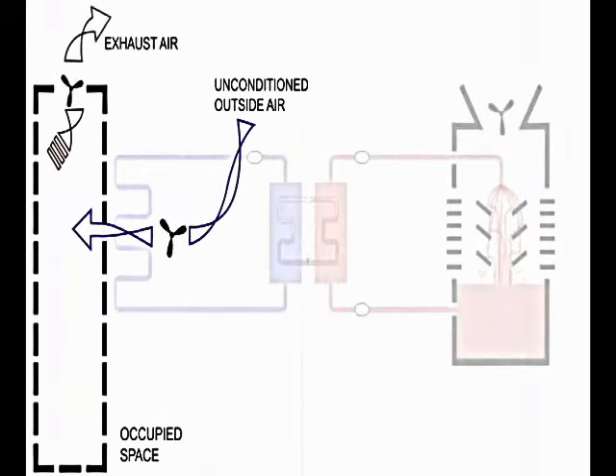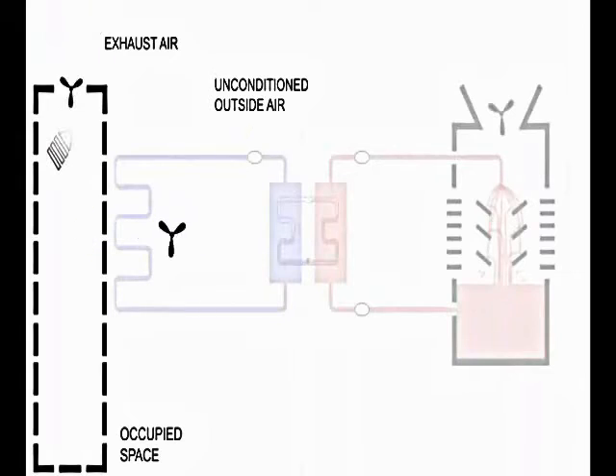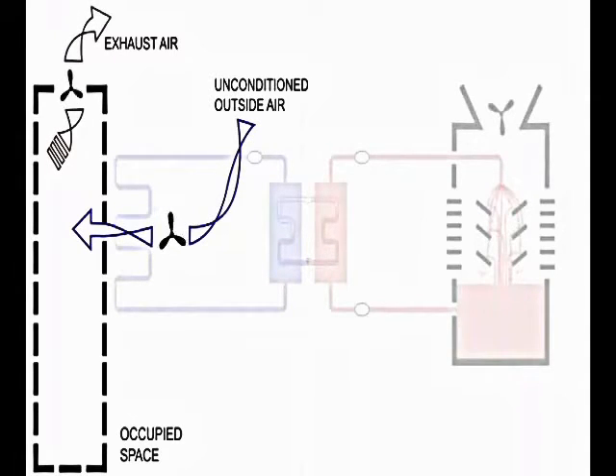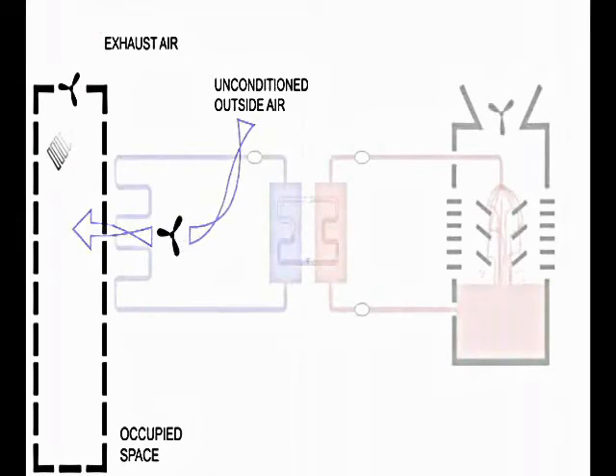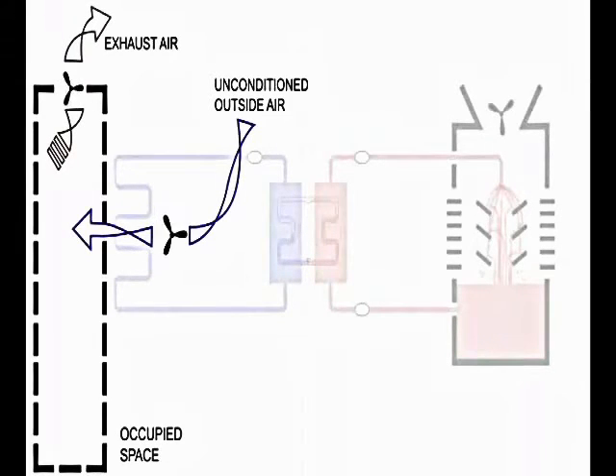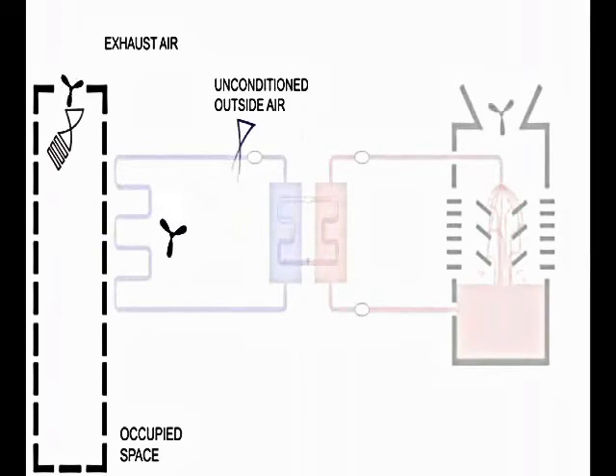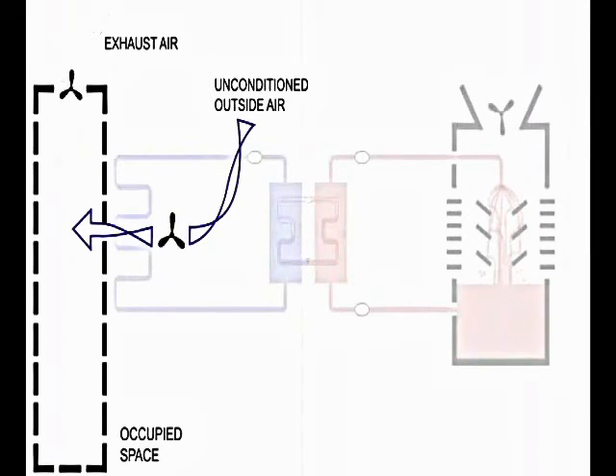Often an economizer cycle is not included in a mechanical package when it really should be. It is free cooling, and even when the economizer mode is available, it is often underutilized by building equipment technicians. That's why it's vital to have the architect, the mechanical engineer, the owner, and the building technician at the table together at the beginning of the design process to get everyone nodding their heads in agreement toward a common goal.